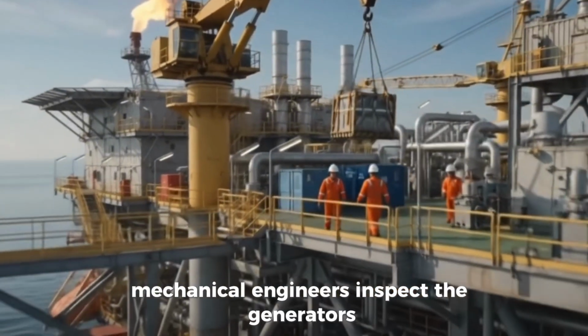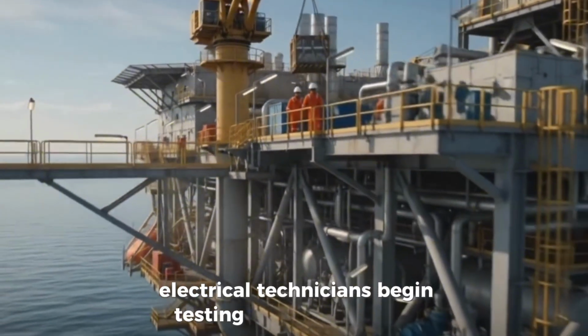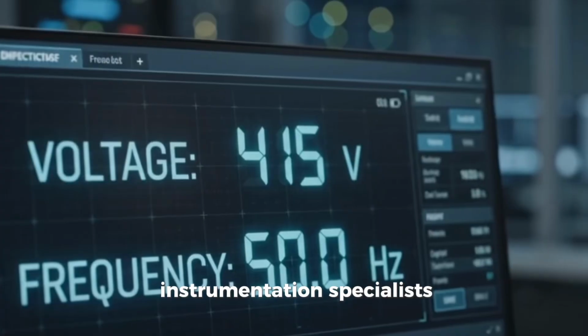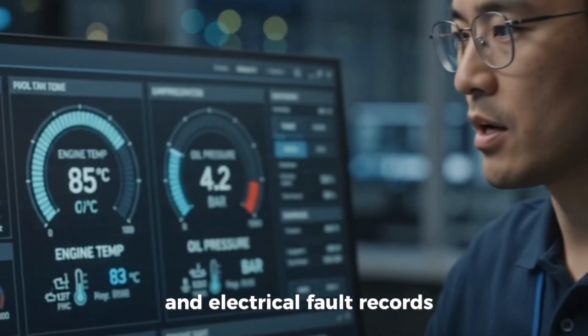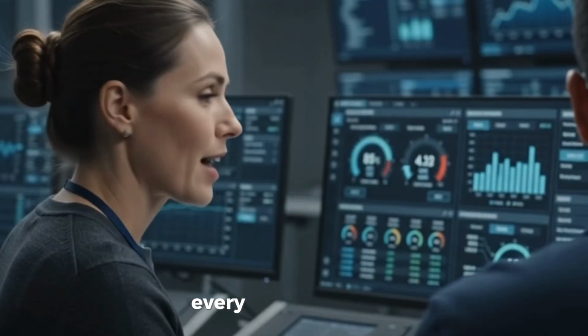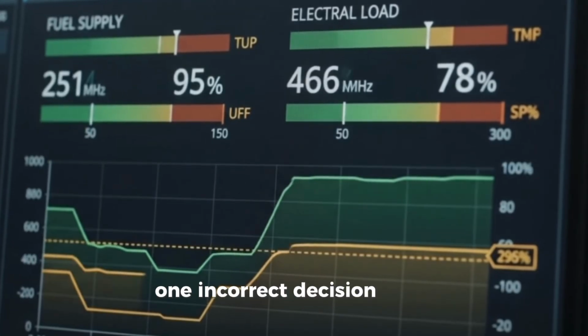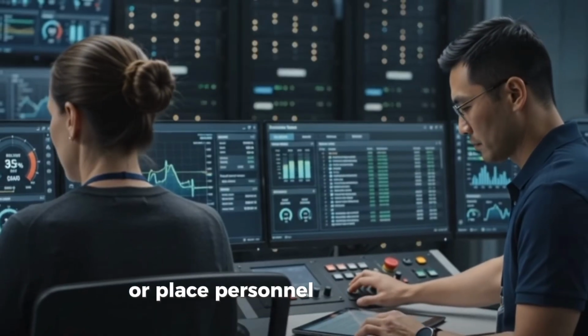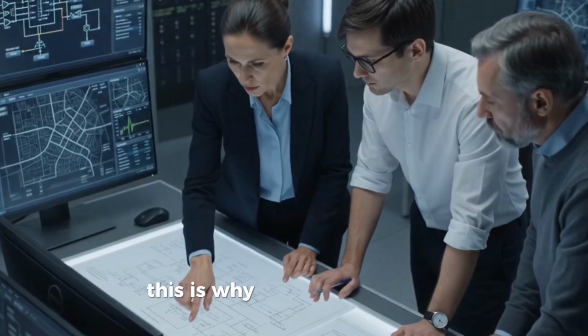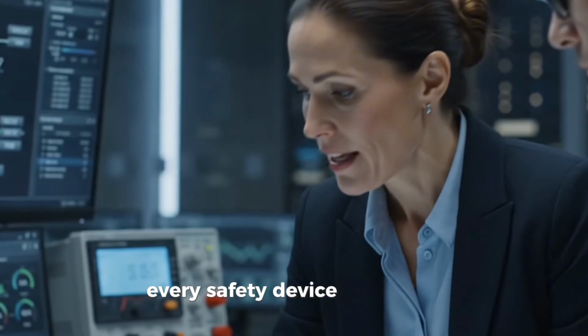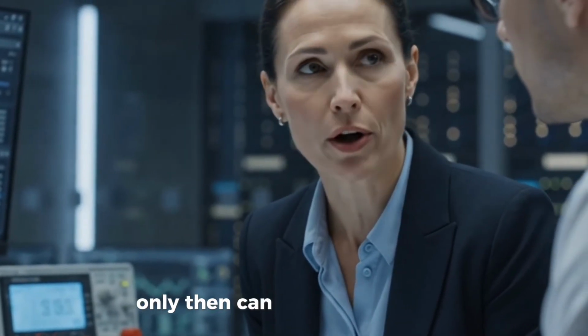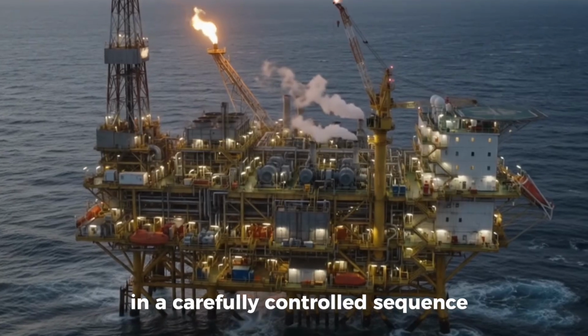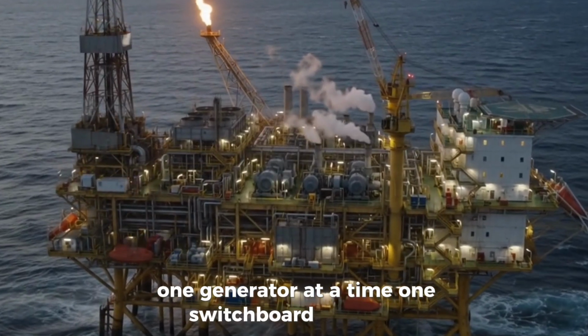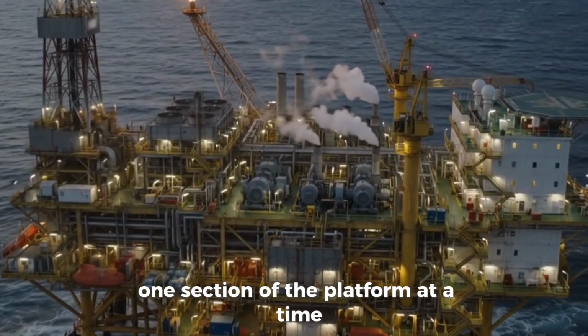Mechanical engineers inspect the generators. Electrical technicians begin testing the switchboards. Instrumentation specialists review protection relays and electrical fault records. Every department works together. Every minute matters. One incorrect decision could damage expensive equipment or place personnel at unnecessary risk. This is why offshore platforms never restart immediately after a blackout. Every system must be inspected, every circuit verified, every safety device confirmed operational. Only then can power be restored in a carefully controlled sequence, one generator at a time, one switchboard at a time, one section of the platform at a time.